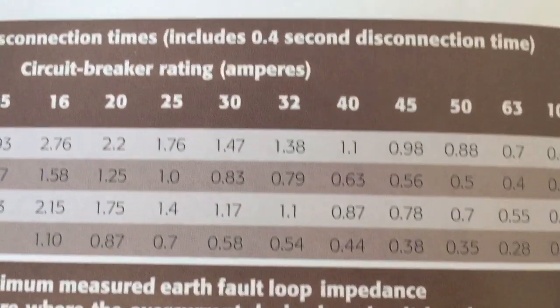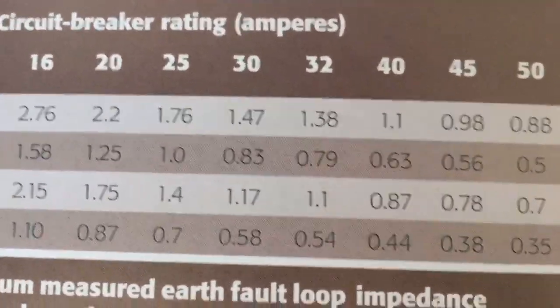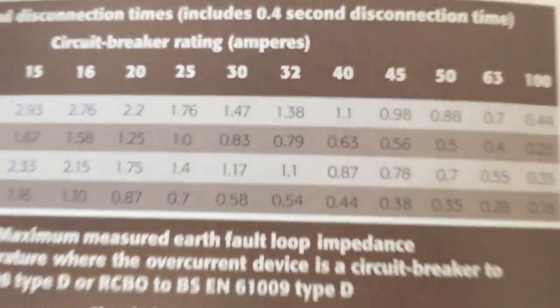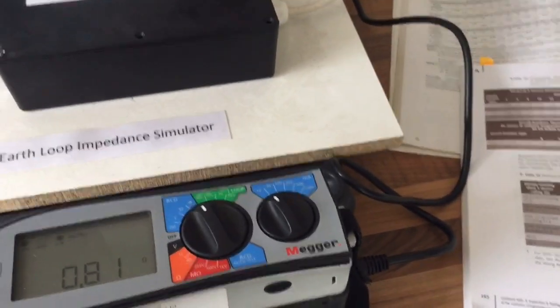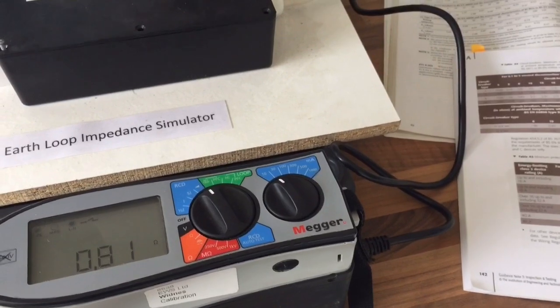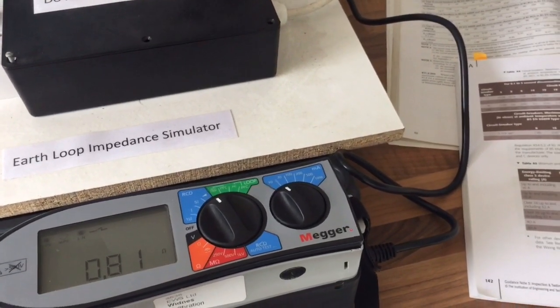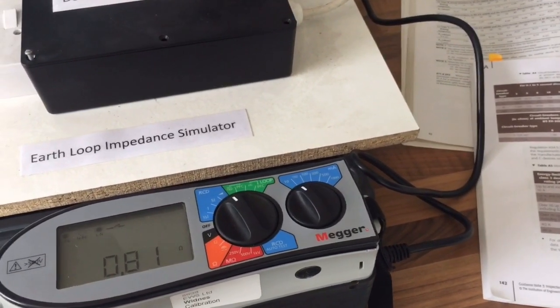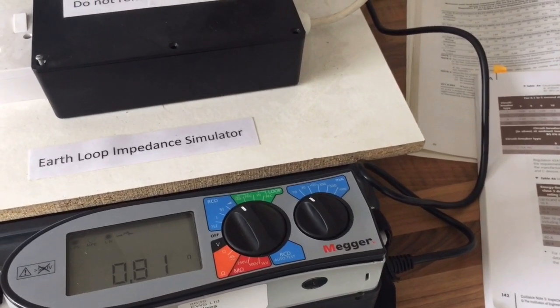Going back to the table, what we were after was 1.1Ω. What that means effectively is that if the earth fault loop impedance is less than that value, that circuit will operate in less than 0.4 of a second under earth fault conditions. That's the whole point of the exercise.